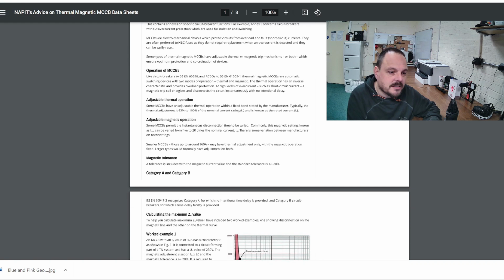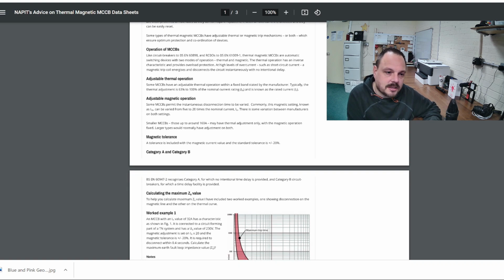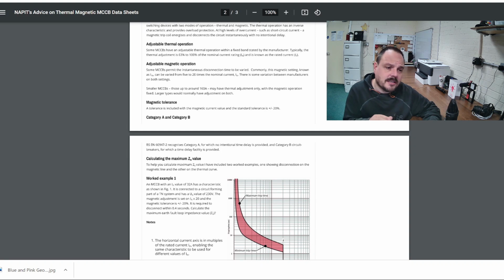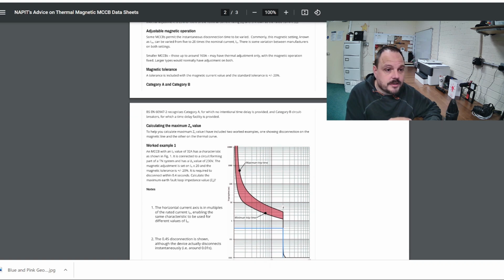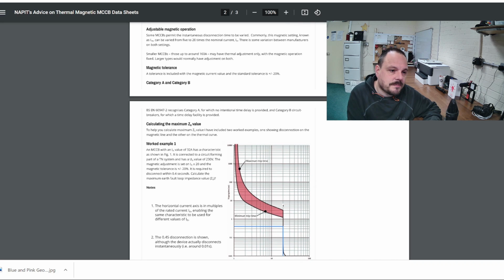Then it talks about the magnetic tolerance. A tolerance is included with the magnetic current value, and the standard tolerance is plus or minus 20%. Explains a little bit about the categories, and again that's on when you're selecting your equipment to be installed. Category A has no intentional time delay. Category B does have time delay facility provided on the actual device. Then it explains how you can calculate the value of ZS.